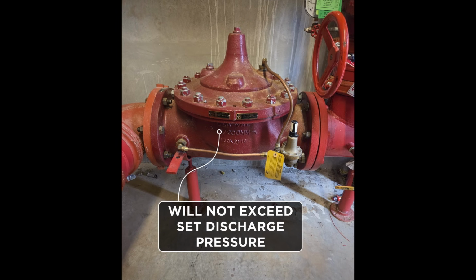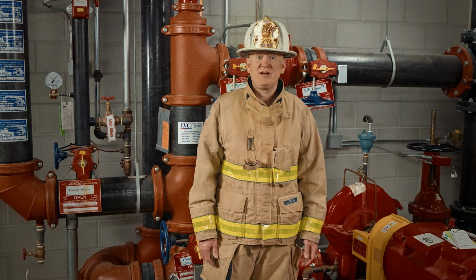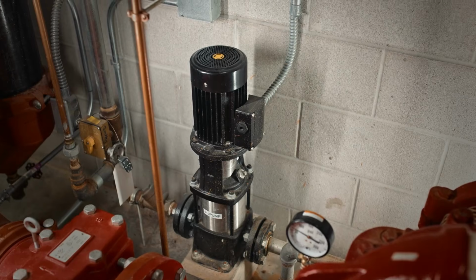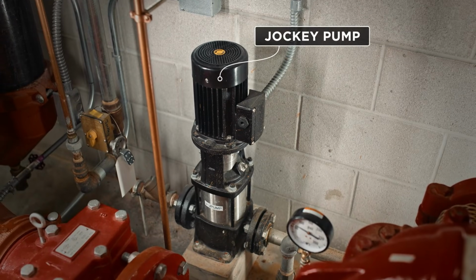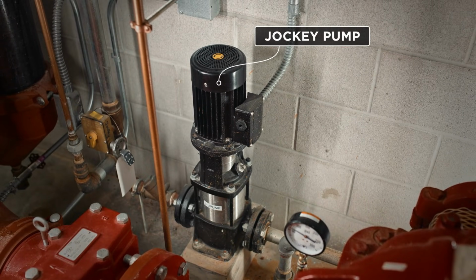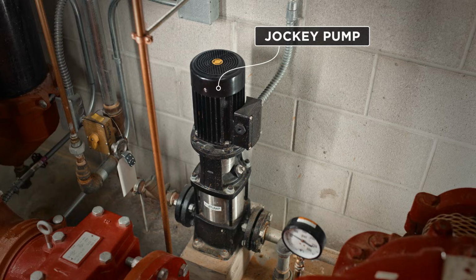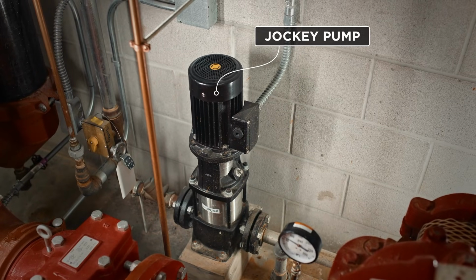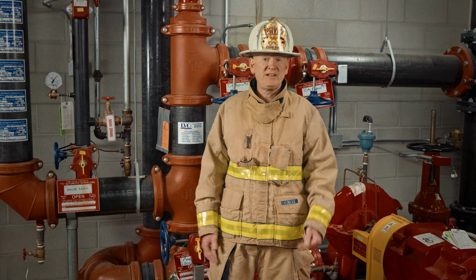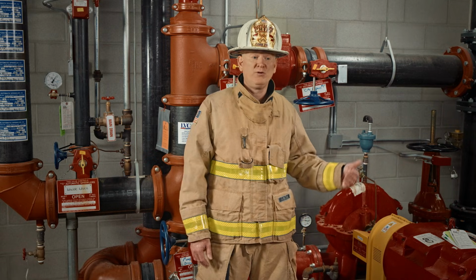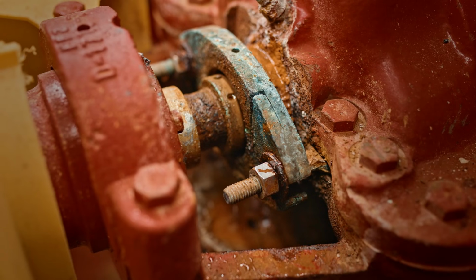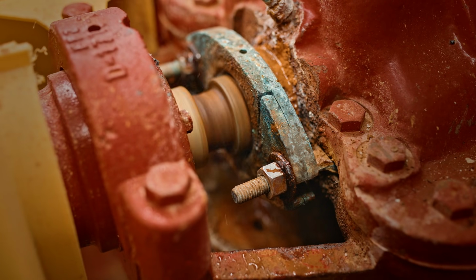than its set pressure. Every fire pump room is also going to have a jockey pump. That's the maintenance pump. It's the one that's used to maintain pressure in the system if there's a small leak or drop in system pressure. A jockey pump will not keep up with the flow of one sprinkler, so if a sprinkler activates or we've opened a hose valve, it will not be able to keep up. That pressure drop will start the main fire pump.